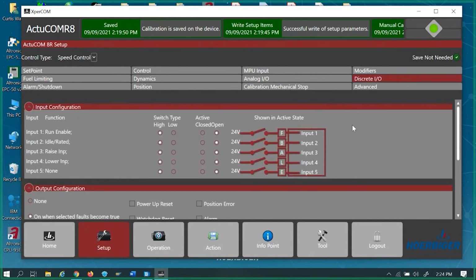Your discretes, these are your inputs to the governor that tells it what to do. So on input number 1 I have it as a high switch. What a high switch means is I'm going to send it a 24 volt DC signal, or I'm going to take it away. A low switch is I'm going to send it a ground signal, or I'm going to take it away. When I send it or take it away, it's through this active open and close. See how the switch closed and it opened?